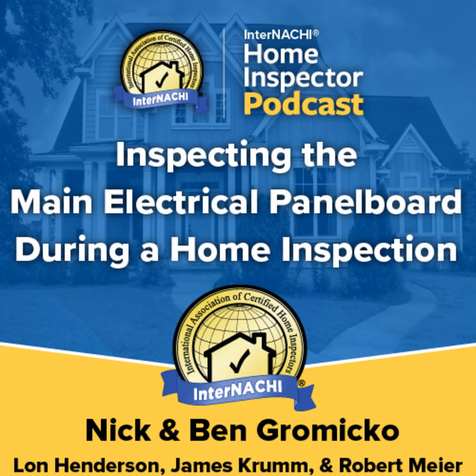Backfeed breakers. Some panels will be supplied with power that enters through a breaker instead of being directly connected to the buses in the panel. This is backward from a more typical configuration. The breaker remains energized even if it is off or removed from the bus. Because this is dangerous, there must be a screw, clamp, or clip that permanently secures the breaker to the panel board so that it cannot simply be pulled off of the bus bars.